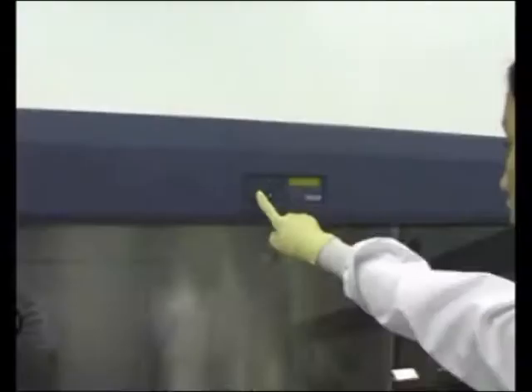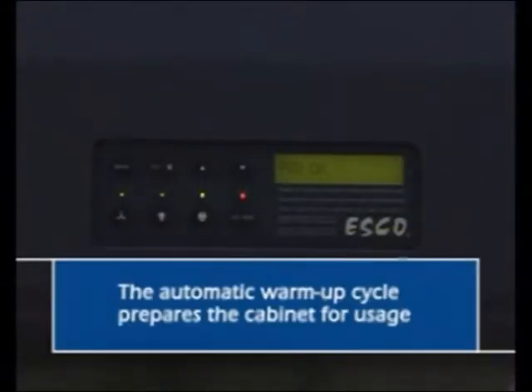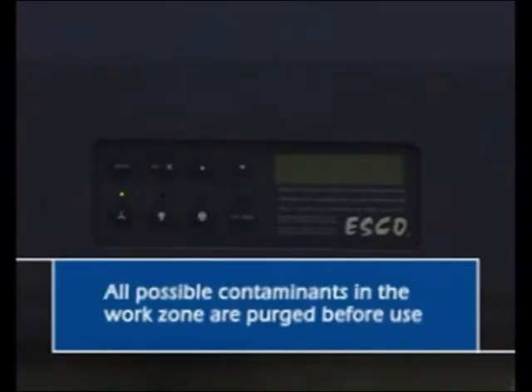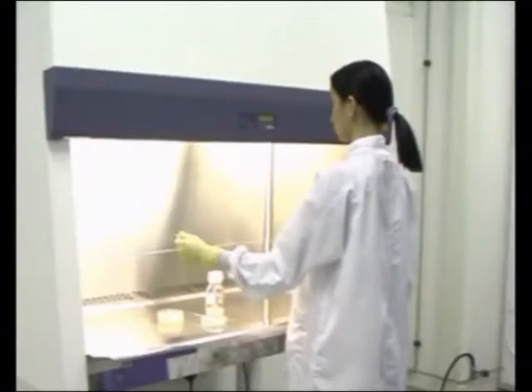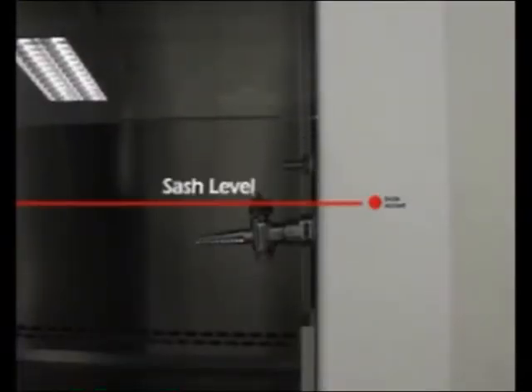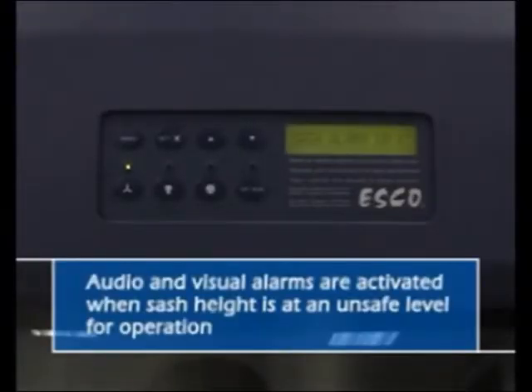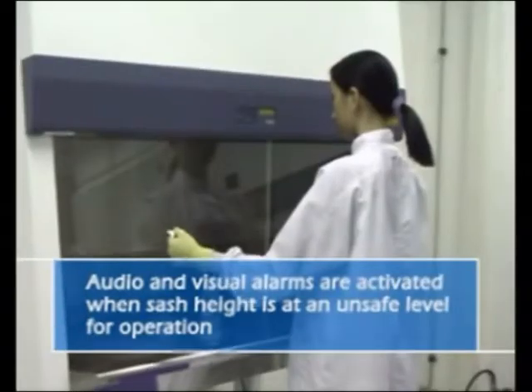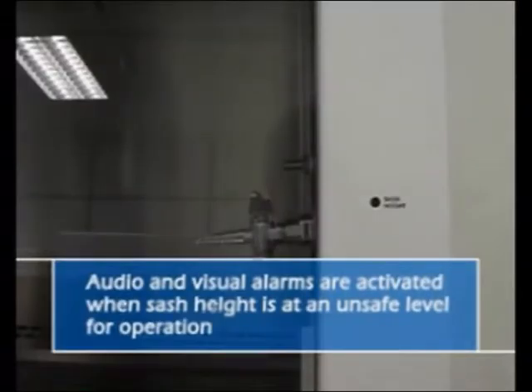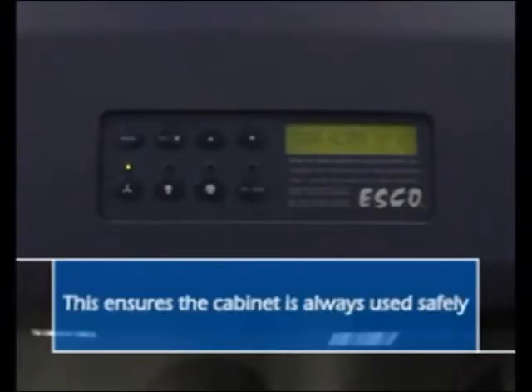The Sentinel microprocessor control has a default warm-up cycle of 3 minutes, during which time the cabinet work zone is purged of all possible contaminants. Audible and visual alarms alert the user of unsafe conditions, such as when the sliding sash is at an unsafe opening height, which may cause airflow disturbances.